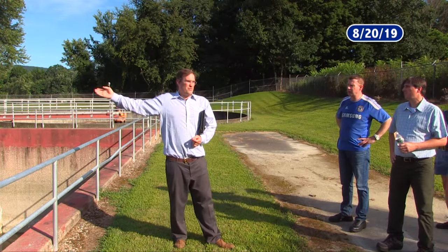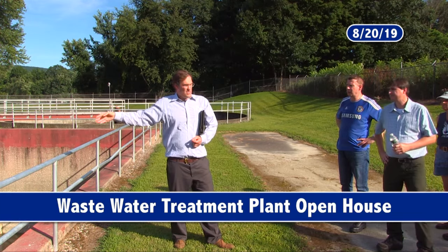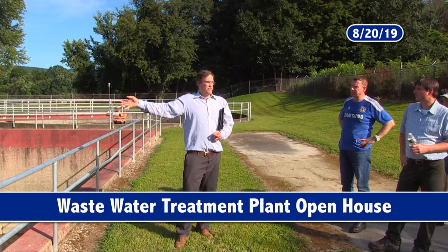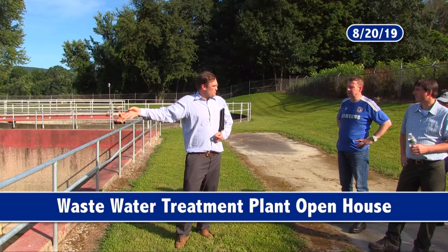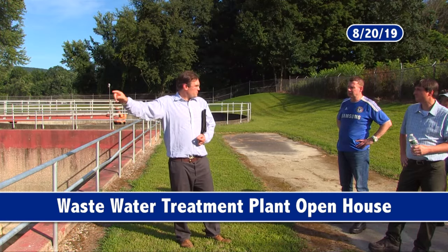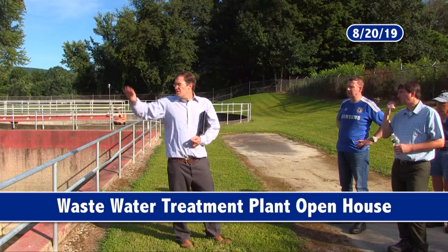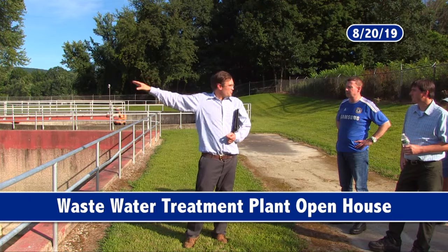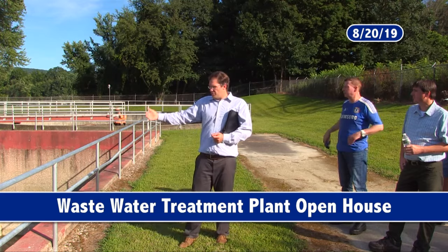To meet the treatment requirements, they only need to run on, Keith, correct me, that's basin one, right? And this is basin two? Yeah. So they only need to run on basin one. So temporarily, you do all the construction you need here in basin two, get this set up in plug flow, get your aeration system in, get your mixers in, you'd switch the flow to here temporarily, coring holes through the walls, making temporary penetrations. You'd run on this during construction, build the other side. On the other side, there'd be a channel to distribute the flow between the two plug flow reactors. And then from there, it would flow plug flow through this tank, through this tank.